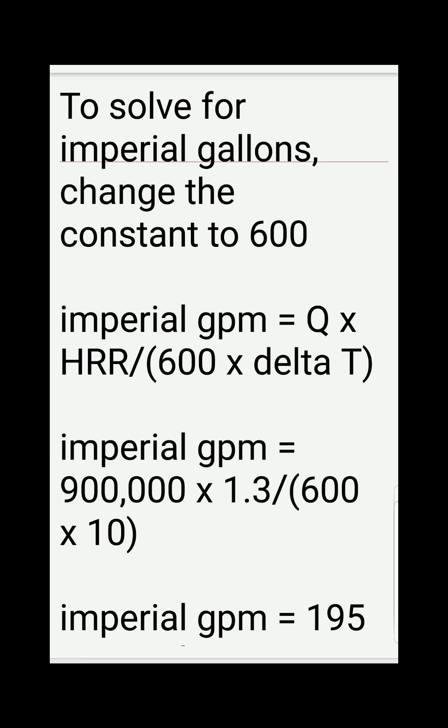Now for the second question, we solve for imperial gallons per minute. To do this, we change the constant in the main equation from 500 to 600. So imperial gallons per minute equals Q (cooling capacity) times HRR, divided by 600 times Delta T.